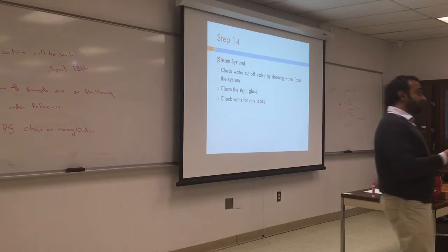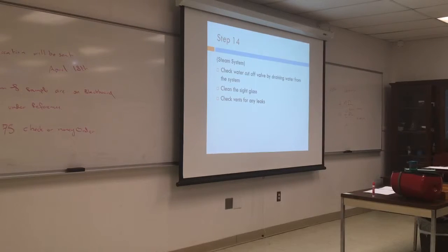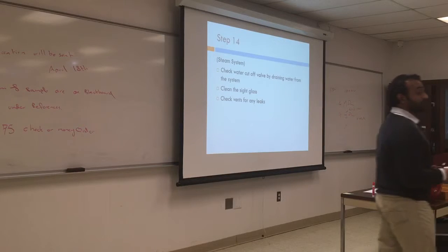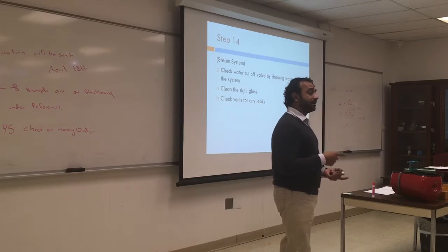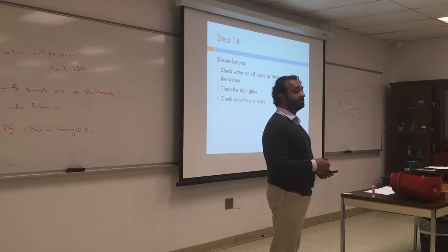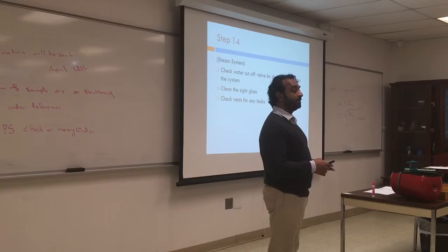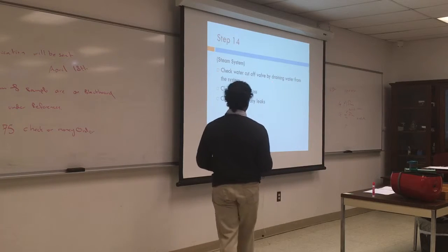And also check for the high pressure cutoff. So turn on, set the pressure at 2 psi and wait. And look at the pressure gauge on the boiler. The boiler must have a pressure gauge on. It tells you what the actual pressure inside is. If you see that the pressure cutoff did not cut off at the set pressure, you might need to change the high pressure cutoff switch.